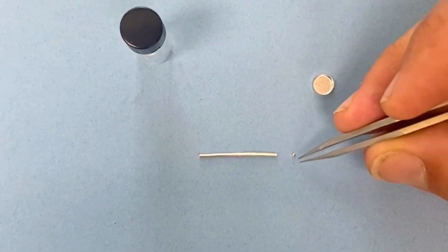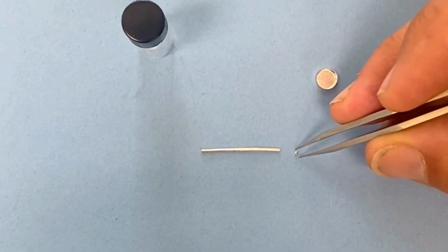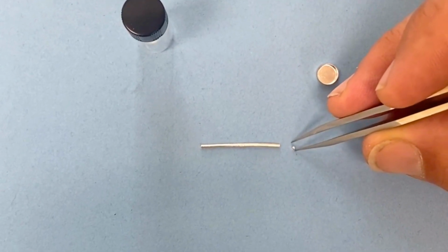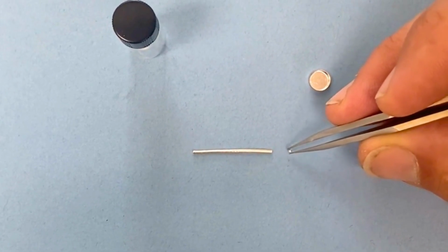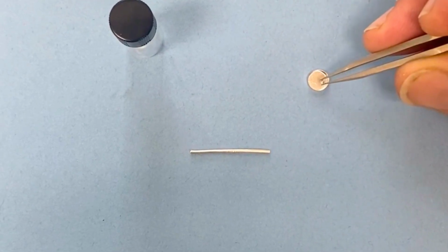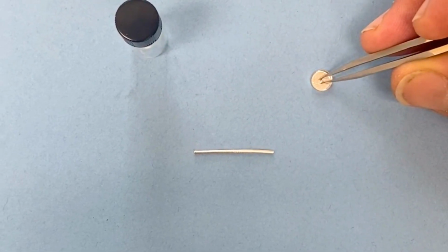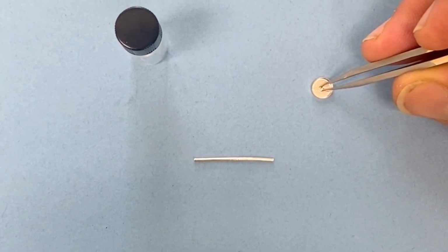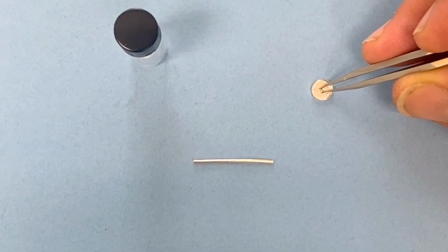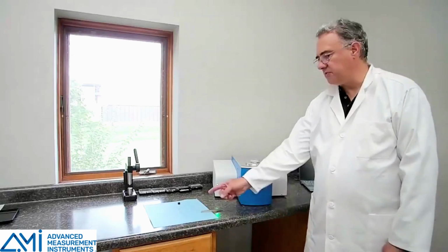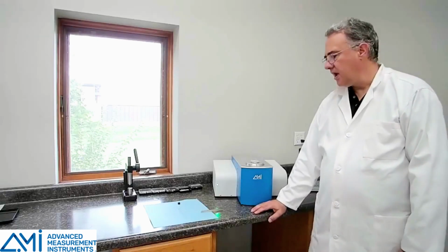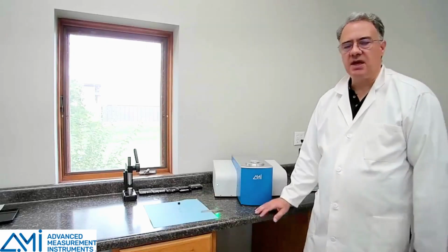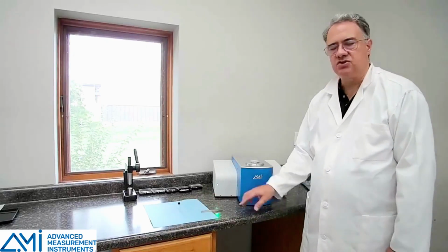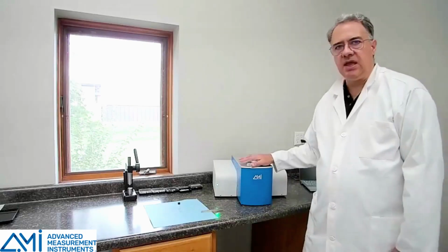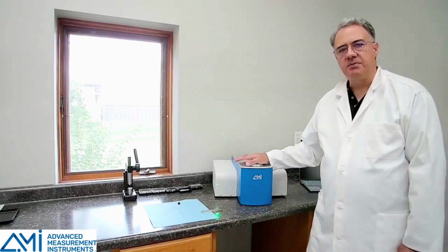I've cut off a section of this wire here, this being indium, and I placed it in here. This one's about 5 milligrams. It's a very small section of this wire, so you can get maybe 100 or more samples just from that section of wire. And what you do is you set it in the very center of the pan so that it gives the best contact with everything and evenly distributed. And then you would set that in your unit and you'd run your calibration.